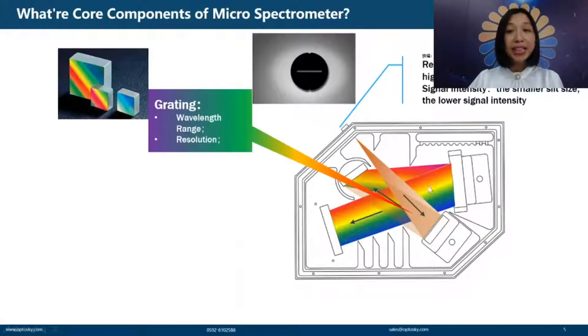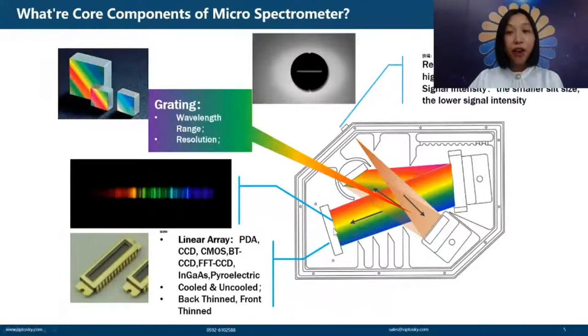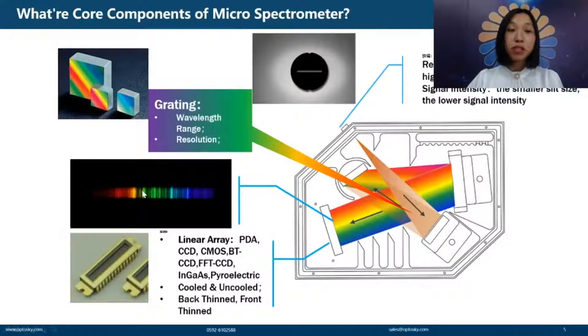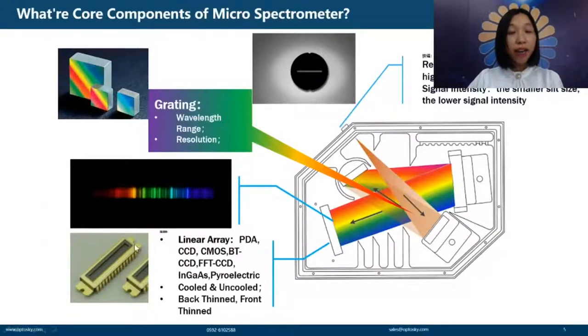Next is the grating — a very important component. It decides the wavelength range and the resolution. Then there is the detector, which transforms optical signals to electrical signals. It forms a spot beam stripe on a linear array, from which we can export the spectrum as electrical signals.